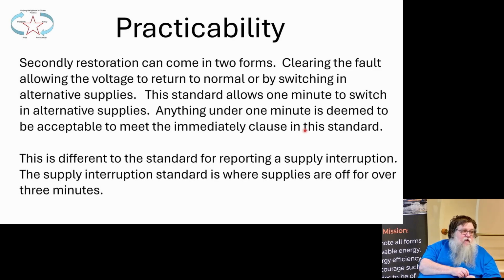It's different to the standard for reporting a supply interruption though. So the standard for reporting a supply interruption, that the DNO has to say that a customer's had 3 interruptions, is that it's got to be off for 3 minutes each time to record a supply interruption. It used to be 1 minute, but it's changed.